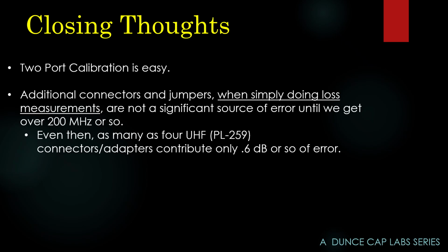Okay, first of all, what we learned is 2-port calibration is easy. And we also learned that additional connectors and jumpers, when simply doing loss measurements, are not a significant source of error until we get up in the UHF range. I underlined doing loss measurements because if you're doing anything having to do with wavelength, testing for reflection or impedance or something like that, then additional connectors and jumpers start to play a role.